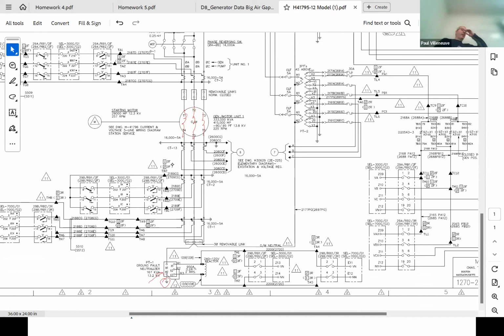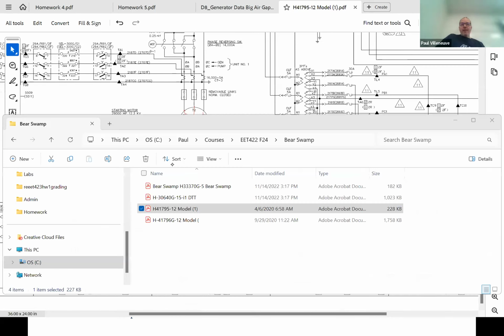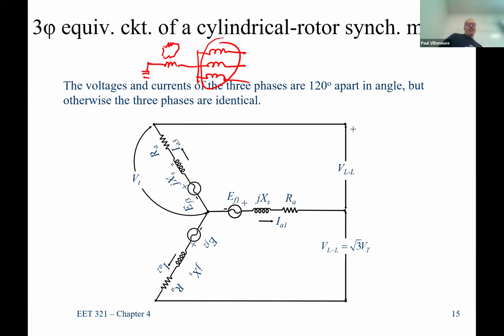They call it a ground fault neutralizer - some of the terms they come up with - it's just a step-up transformer. Actually, it's a step-down transformer, and that's how you would actually see all three windings. So what we showed here is all three phases, but you would never usually see that. You don't even show the X and R values because we're not modeling it from a power flow perspective.